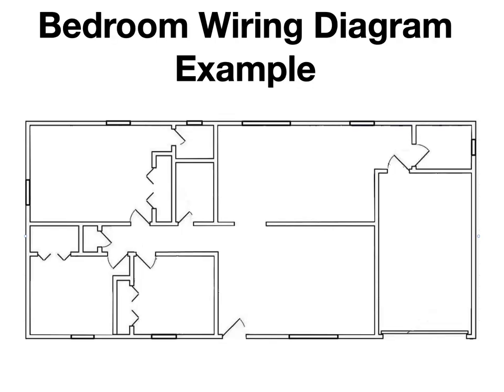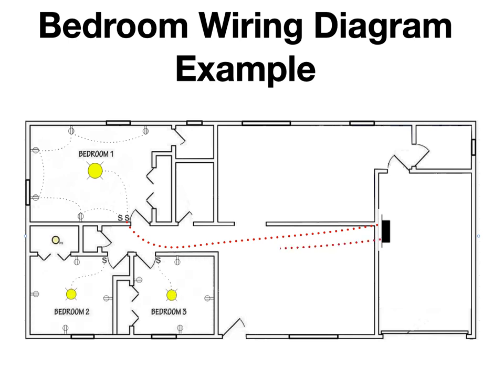To start with, let's look at the details that can be added to the bedroom wiring, starting with bedroom number one. Locating the power panel in the garage, the first feed wire will be connected to the two-gang switch box in this bedroom next to the door. One switch will control the ceiling light, and the second switch will control the tops of the duplex plugs in the bedroom. A second circuit will bring power to bedrooms two and three, starting at the closest duplex plug of bedroom three. The power will then extend to the two adjoining duplex plugs, as well as bringing power to the bedroom light switch, which controls the overhead light. We will connect the switch to the bedroom overhead light with a 14-3 cable wire.